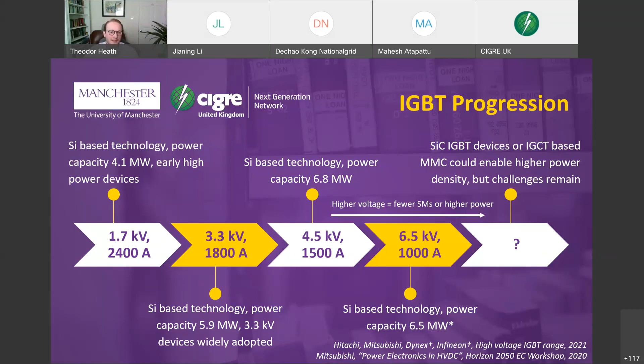So next, on to the lowest TRL in this multi-terminal grid consideration, which is DC to DC converters. When HVDC systems are designed to work together with matching DC voltage levels, there isn't really a need for DC to DC converters, other than for secondary systems potentially stepping down for consumption at lower voltage levels. However, in the future, if we're looking at this supergrid scenario, we may wish to interface pre-existing plus or minus 320 kV systems to the next generation systems of plus or minus 400 or 500 kV. So we may need to consider this technology as something in our arsenal later on, even if we don't require it right now.